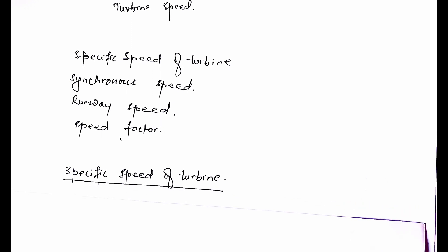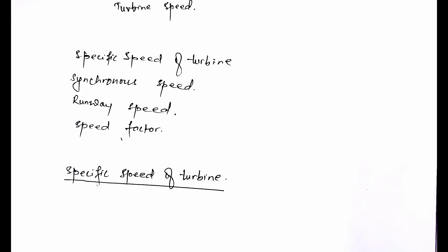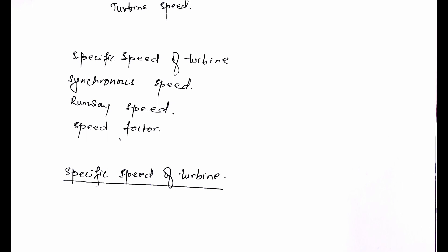The specific speed of a turbine is the speed at which the machine produces one horsepower under one meter head. It is an important parameter for the design of the turbine, as it includes all three basic parameters: speed, power, and head of the turbine.